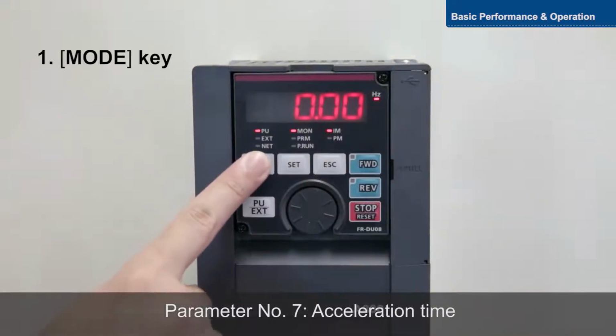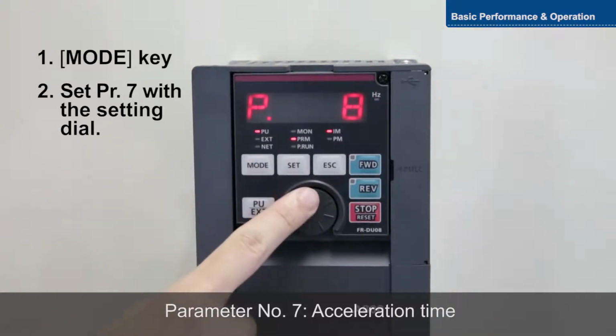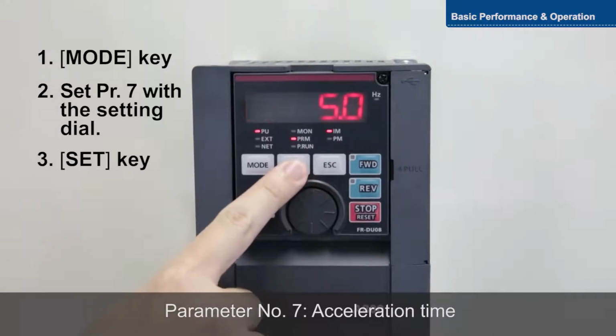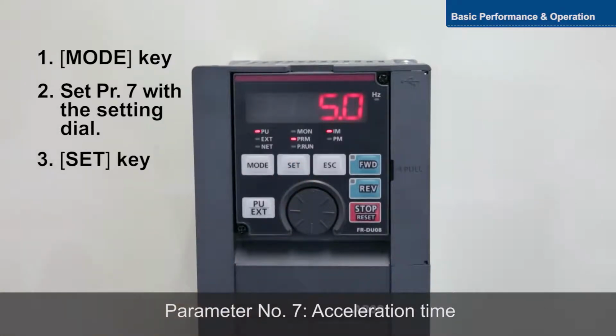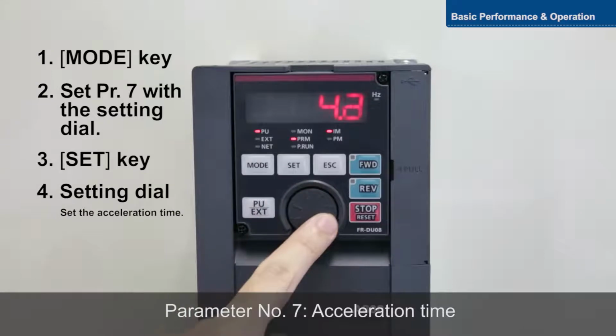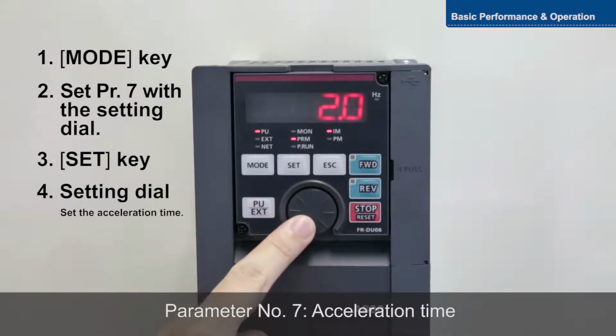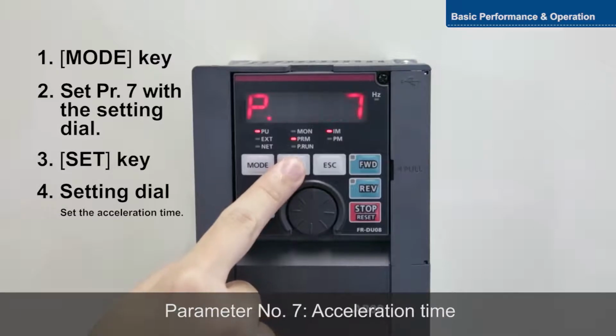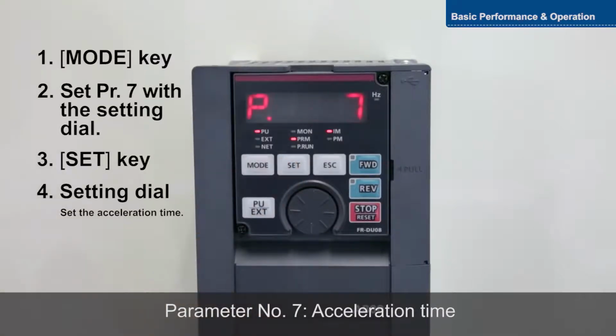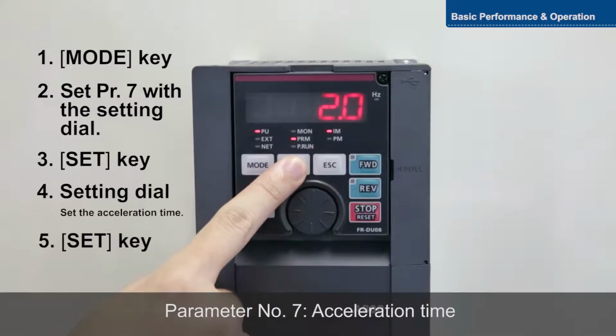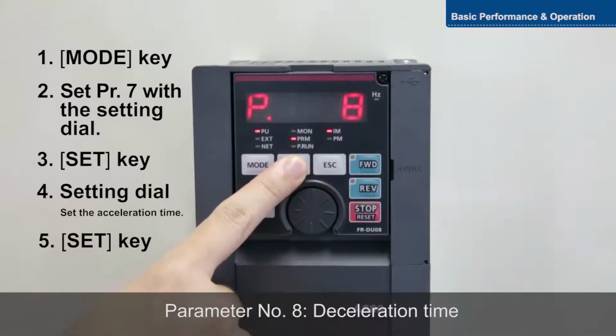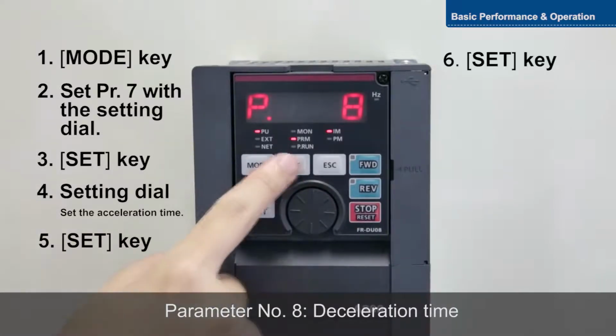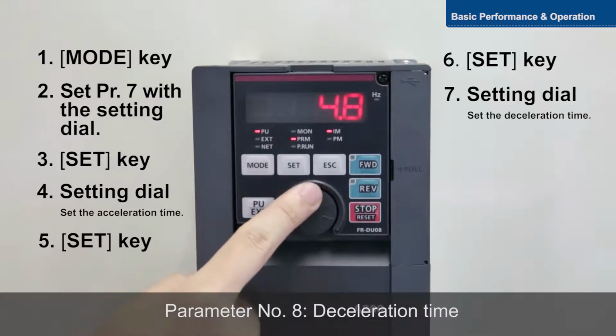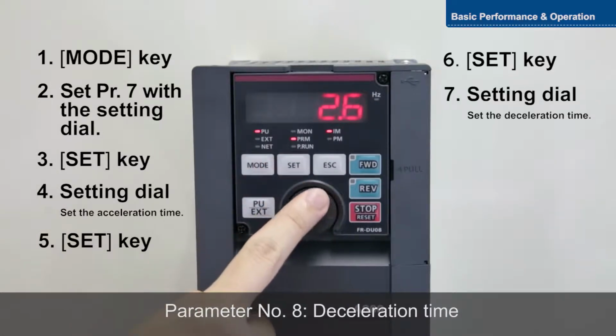To set parameter 7, push the mode key, select parameter setting mode, and turn the setting dial to 7. Parameter 7 sets the acceleration time from when the motor starts until it reaches the reference frequency. Parameter 8 sets the deceleration time from the reference frequency until the motor stops.